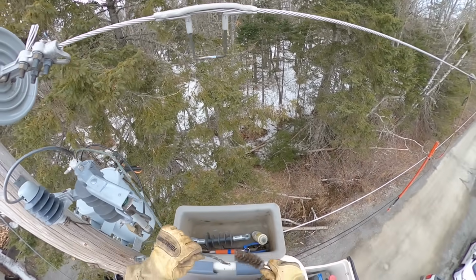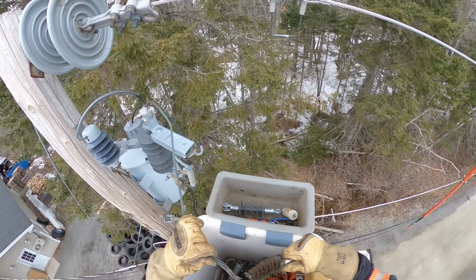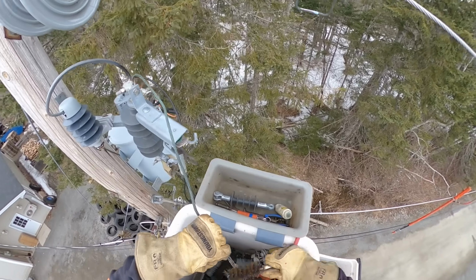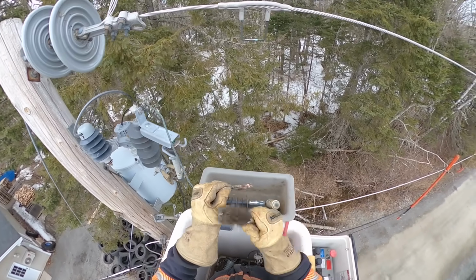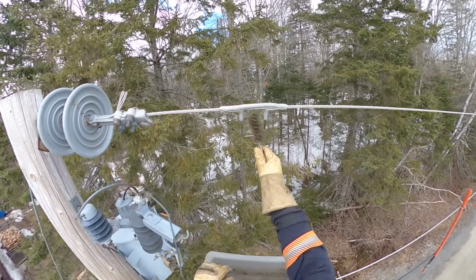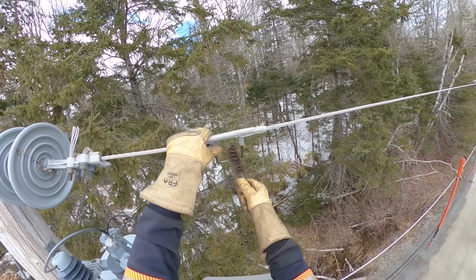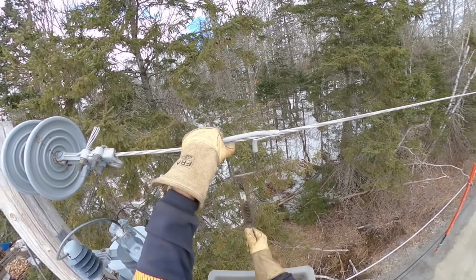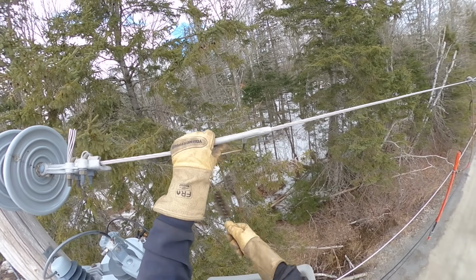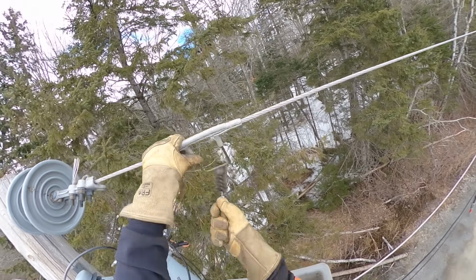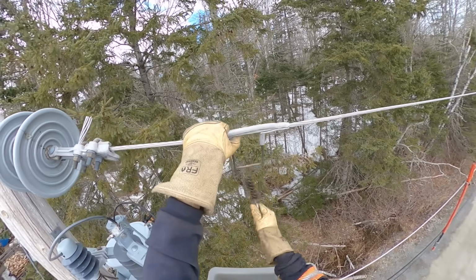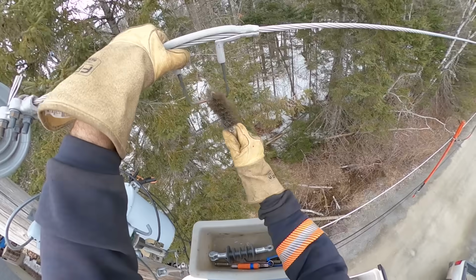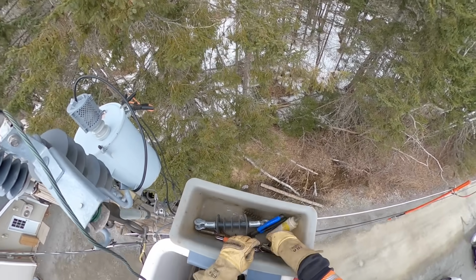But we'll give this piece of copper some brushing. I could have replaced that little piece if I needed to, but it's not necessary as long as we get the connection shining. And we got to get rid of all that corrosion on the stirrup. The stirrup is still good. There's no sense in replacing that. If it had burnt up or if it was pitted real bad for any reason, I would have used a new stirrup, one of the bolt-on type that we can install with our grab all.